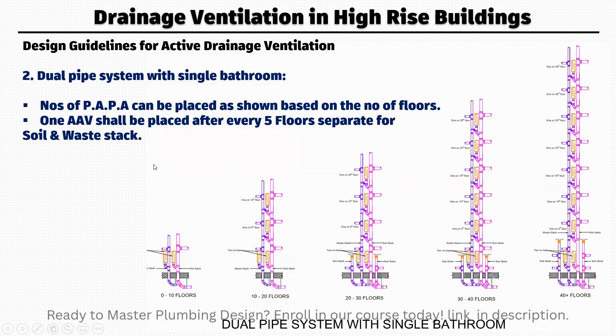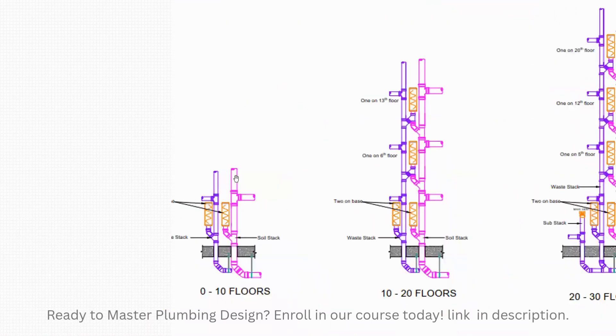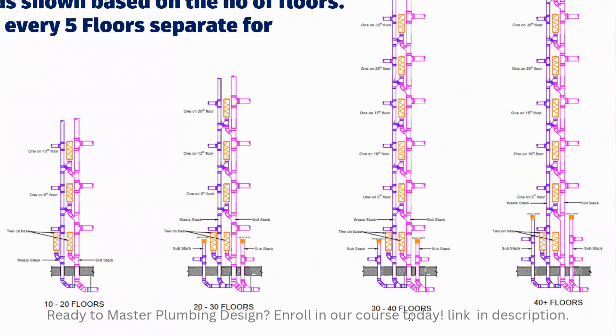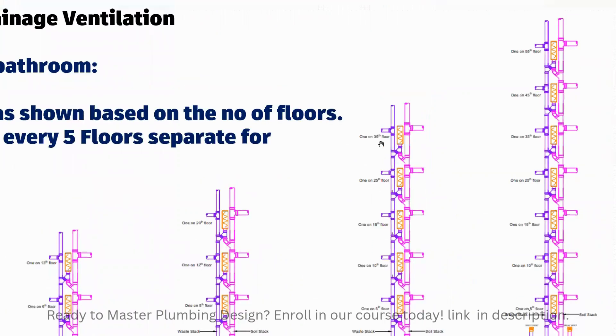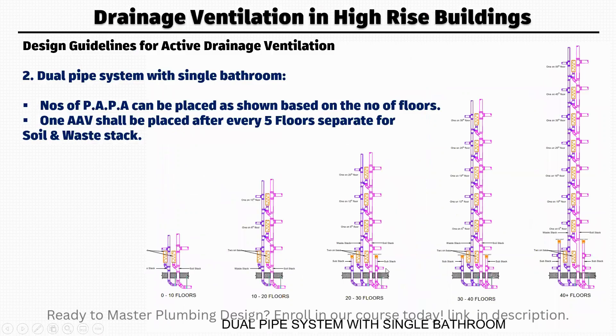For the dual pipe system, the same logic applies. The difference is there are two stacks — one for soil and one for waste. For example, for thirty to forty floors you need AAVs on the fifth floor, then tenth, fifteenth, twenty-fifth, and thirty-fifth. One air admittance valve shall be placed after every five floors, separately for the soil stack and the waste stack.